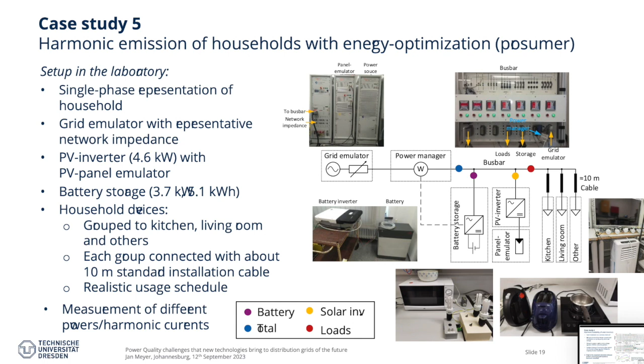The other thing is that we usually allocate emission limits for devices or customers based on its rated power. Because it's fairly the way that if I have a 630 kVA transformer and this is fully utilized, then I should meet the global contribution somehow. And the one that basically has higher power connected, higher contracted power, usually pays more, that's why he should also get more emission. But if I have no energy that I consume, I should also have no emission. And that's maybe a little bit strict, but formally it should be that way.